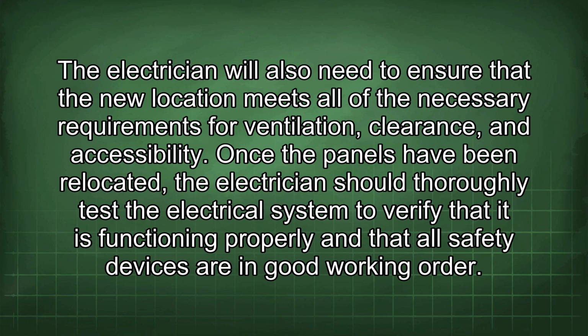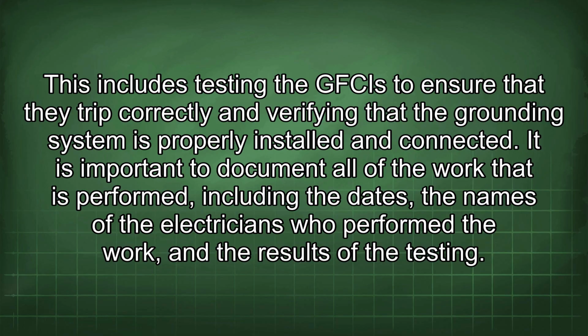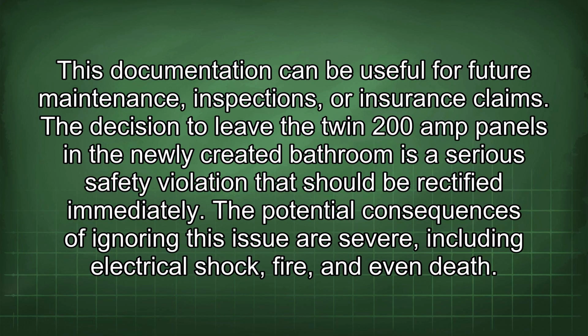The electrician will also need to ensure that the new location meets all of the necessary requirements for ventilation, clearance, and accessibility. Once the panels have been relocated, the electrician should thoroughly test the electrical system to verify that it is functioning properly and that all safety devices are in good working order. This includes testing the GFCIs to ensure that they trip correctly and verifying that the grounding system is properly installed and connected. It is important to document all of the work that is performed, including the dates, the names of the electricians who performed the work, and the results of the testing. This documentation can be useful for future maintenance inspections or insurance claims.